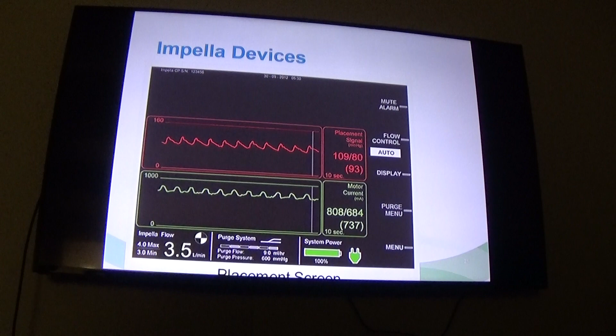So if you have to troubleshoot and transport, probably the most common event you're going to see is a suction event. It occurs when the preload is too low, so you may see that on your central line, your CVP monitor, maybe, if you have it. Or you can just put the ultrasound on, and if the person has a completely collapsible IVC and a very small left ventricle, you're probably having a suction event, just like you would with an LVAD. So your temporary fix is you're going to select the soft key, that second one down on that soft key menu, and reduce by 1 to 2 P levels. This will take some of the work off the heart, or some of the work off the Impella, and allow the heart more time to fill.